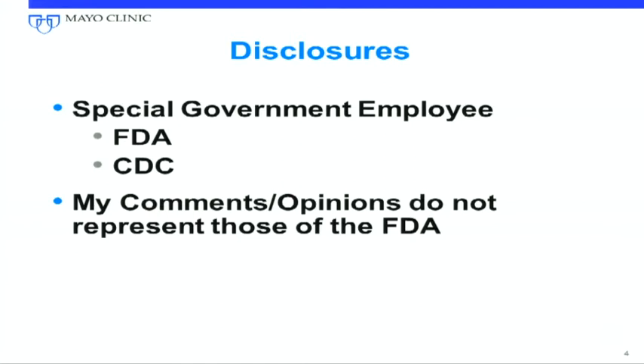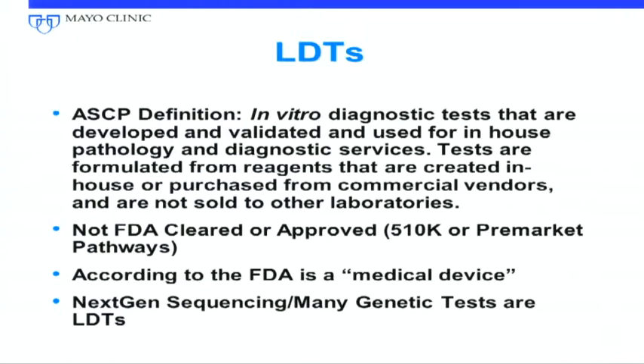What is a laboratory-developed test? The American Society for Clinical Pathology definition: diagnostic tests developed, validated, and used in-house for diagnostic services. These are not FDA-cleared or approved, and according to the FDA they are medical devices. CLIA does not approve tests — they oversee the environment where testing is done. We don't send a test to CLIA for approval. You can go on the web and pay a few hundred dollars and get a CLIA number and be in business for a period of time until you get caught.